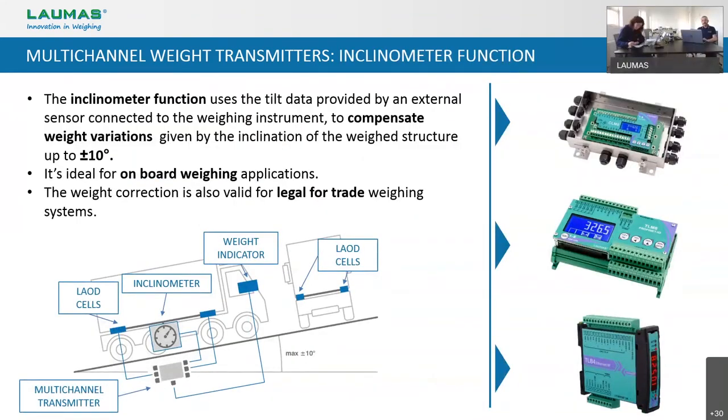In this slide we can see another feature that is common for all of our multi-channel transmitters: the inclinometer function. It consists of an inclinometer sensor connected via serial communication to our weight transmitters. The combination of the two devices allows you to compensate the weight variation given by the inclination of the weighing system, up to a maximum of plus or minus 10 degrees. We developed this useful function especially for onboard weighing systems, because it can happen that a truck or a forklift, for example, are not working on a flat road. We all know that if the ground is inclined, the weight value changes — so thanks to this feature, we can have perfect weighing even in those conditions.